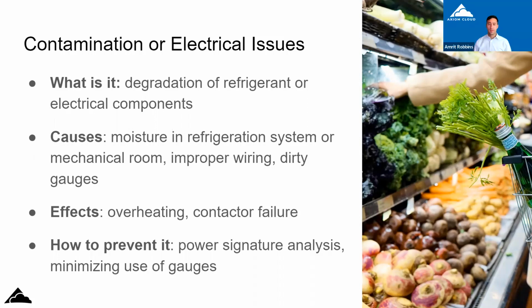And so, Joe, you were mentioning that obviously this can snowball into a very, very expensive on-site repair. Can you talk about why that is relative to warranties and cranes and whatnot? Yeah, I mean, a compressor, not only the compressor itself is expensive, but everything that goes into it. If it's done right, you're going to change contactor controls to test them. If they're old, I always recommend changing them regardless, because it's what protects the compressor. So if you're putting in an investment for the customer, I always change out the controls unless we know they're brand new, because they're there to protect that compressor.